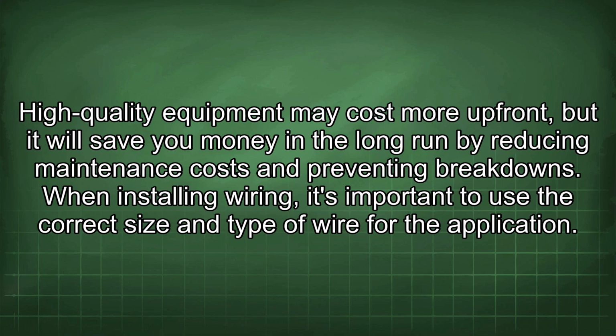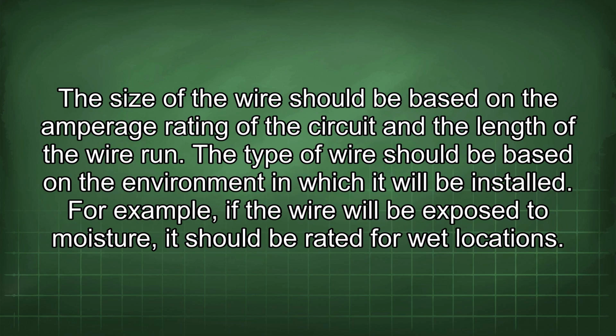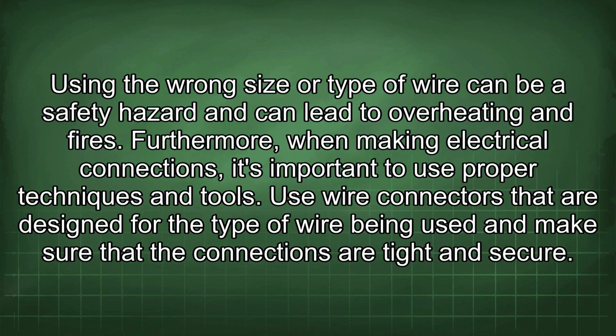and preventing breakdowns. When installing wiring, it's important to use the correct size and type of wire for the application. The size of the wire should be based on the amperage rating of the circuit and the length of the wire run. The type of wire should be based on the environment in which it will be installed. For example, if the wire will be exposed to moisture, it should be rated for wet locations. Using the wrong size or type of wire can be a safety hazard and can lead to overheating and fires.